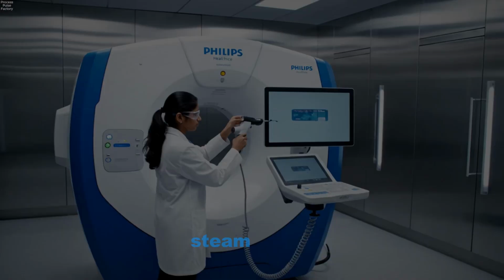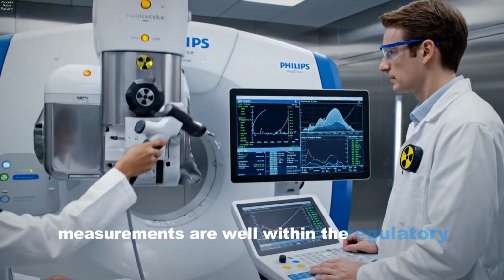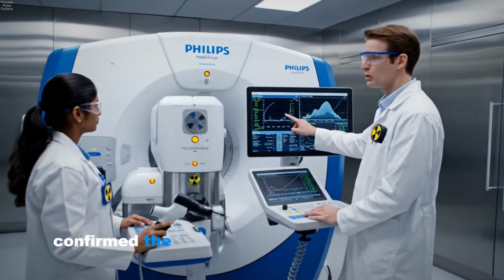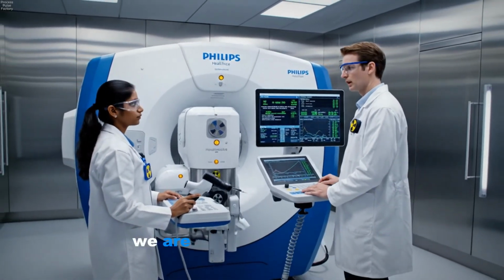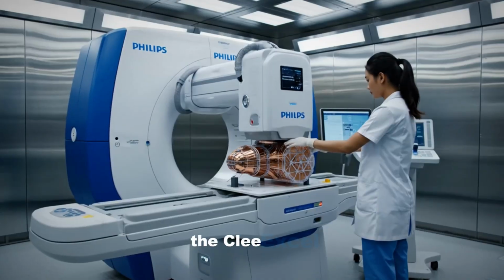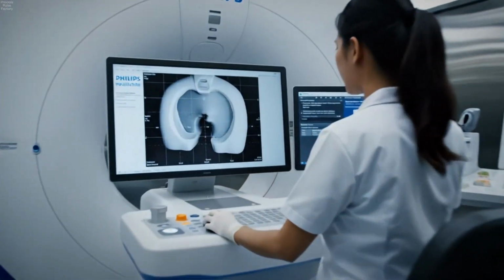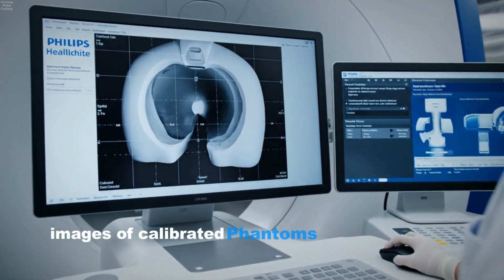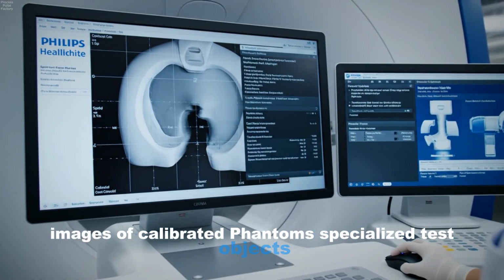Beam quality measurements are well within the regulatory limits. Confirmed. The tube housing leakage is nominal. We are cleared for shipment. The complete X-ray system produces images of calibrated phantoms, specialized test objects.